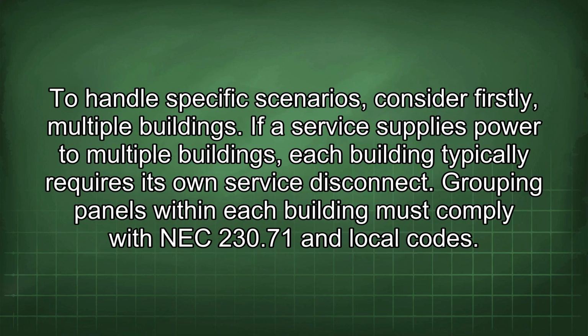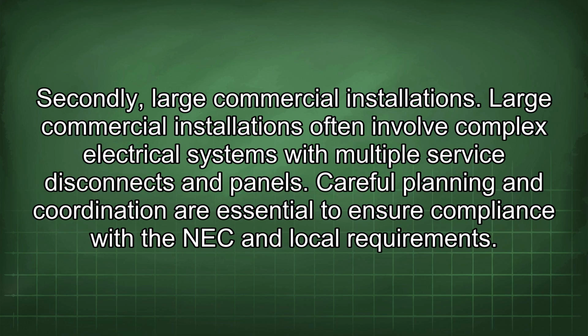To handle specific scenarios, consider firstly multiple buildings. If a service supplies power to multiple buildings, each building typically requires its own service disconnect. Grouping panels within each building must comply with NEC 230.71 and local codes. Secondly, large commercial installations. Large commercial installations often involve complex electrical systems with multiple service disconnects and panels. Careful planning and coordination are essential to ensure compliance with the NEC and local requirements.